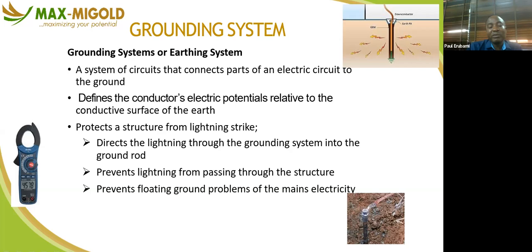The earth helps to correct any form of abnormality in your installation. Maybe overcurrent, leakage current. You cannot tell me your installation is guaranteed, that there is no leakage current. There will be times when there will be leakage current. You may not be there to say, oh, let me protect this. No, the earth helps to correct that. Minimize risk to your installation and your building.